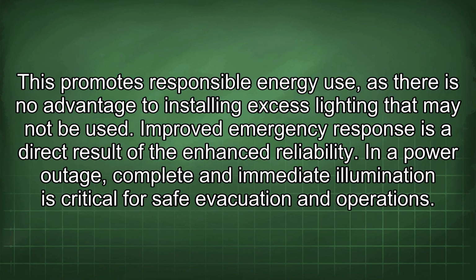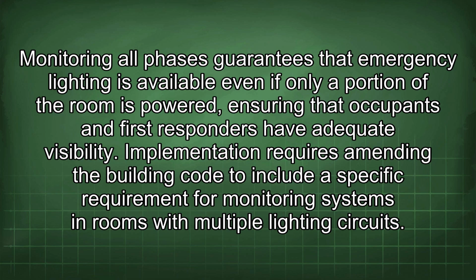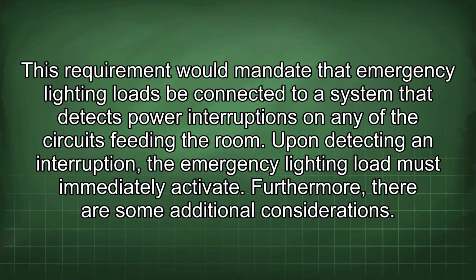Improved emergency response is a direct result of the enhanced reliability. In a power outage, complete and immediate illumination is critical for safe evacuation and operations. Monitoring all phases guarantees that emergency lighting is available even if only a portion of the room is powered, ensuring that occupants and first responders have adequate visibility. Implementation requires amending the building code to include a specific requirement for monitoring systems in rooms with multiple lighting circuits. This requirement would mandate that emergency lighting loads be connected to a system that detects power interruptions on any of the circuits feeding the room. Upon detecting an interruption, the emergency lighting load must immediately activate.